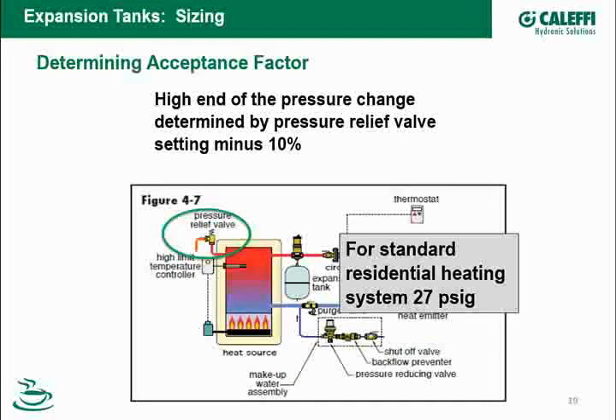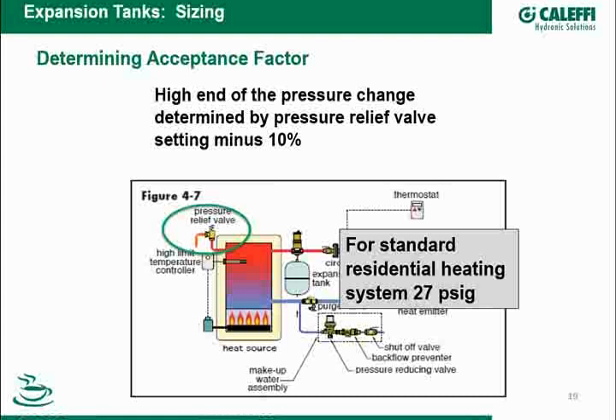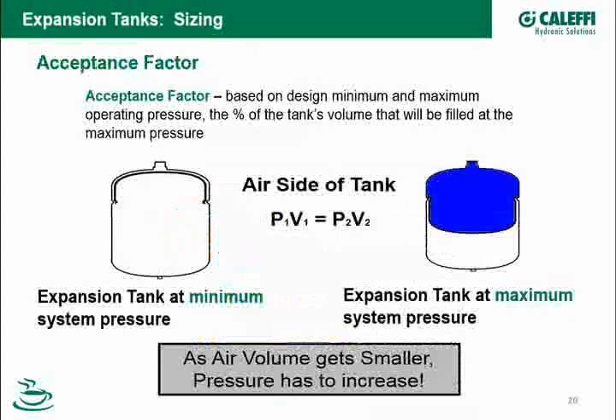Okay. Now, why do we need that change in pressure? It's about accommodating air in the tank. I am going to compress the air, but because of something called Boyle's law, which is P1V1 equals P2V2 in the center of the screen, that's an interpretation of Boyle's law. As I compress the air, the pressure in the tank on the air side has to go up. Okay? So when we start to look at system design, this is why with an expansion tank, I can't fill that tank all up with water. There's always going to be a portion of the tank that's water and a portion of the tank that's air. And this equation actually determines how much water I can put into it, and it's really based on the pressure range the tank's going to be cycling through.